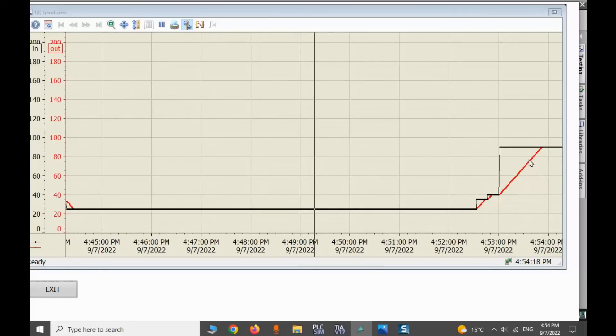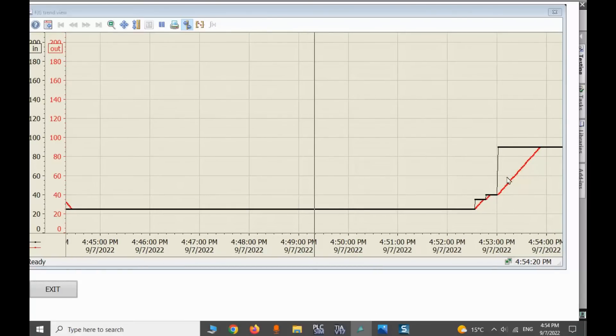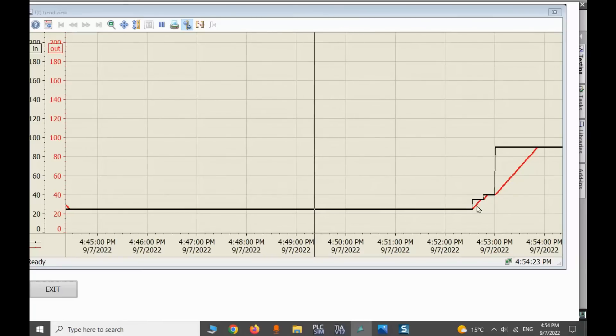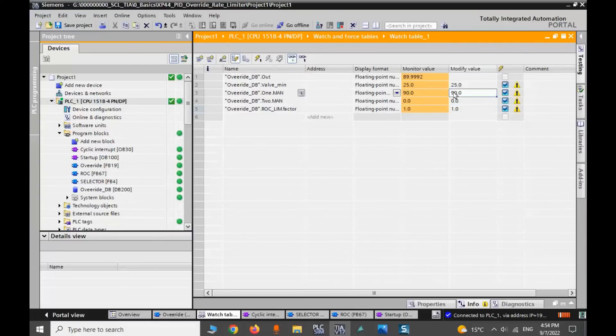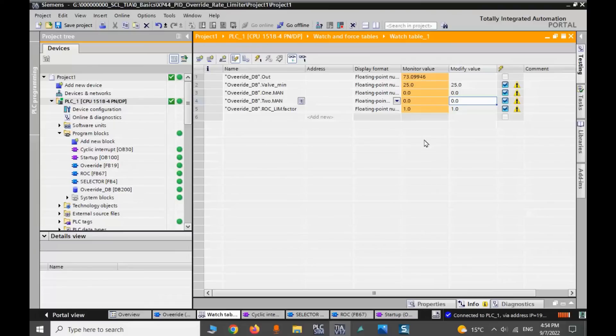You can see that we reach the maximum. Now we will put one of the PID outputs to zero, and you can see that we move quickly to 25 — 25 is the minimum value, and we go directly to 25. I'll pause the video here. You have the source project and you can play with this override selector, and we move to the next topic.